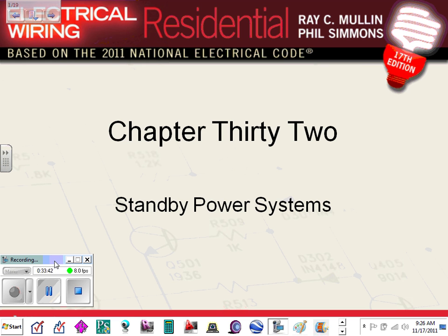Very interesting and very important, because it will prep you guys for sizing generators for an emergency system as well as a standby system. The NEC code has three very important systems. System number one, Zach, my friend, is called the emergency system. These systems have to come up within 10 seconds. A major part of it is the egress signs, exit signs and egress lights. So that's within 10 seconds, emergency system.